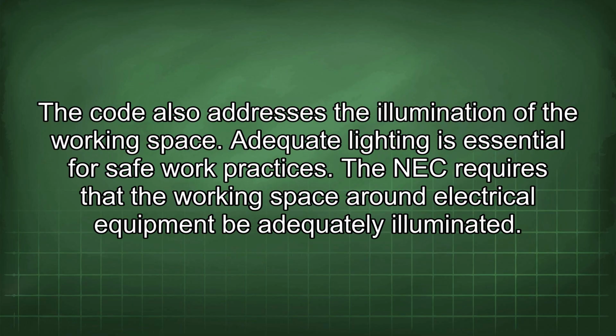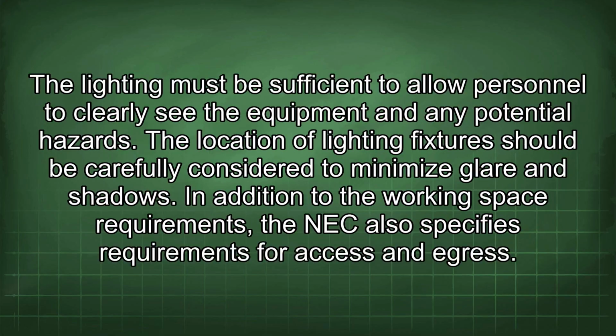The code also addresses the illumination of the working space. Adequate lighting is essential for safe work practices. The NEC requires that the working space around electrical equipment be adequately illuminated. The lighting must be sufficient to allow personnel to clearly see the equipment and any potential hazards. The location of lighting fixtures should be carefully considered to minimize glare and shadows.